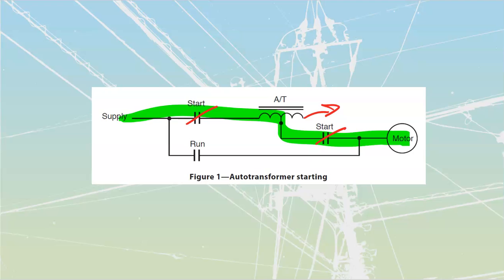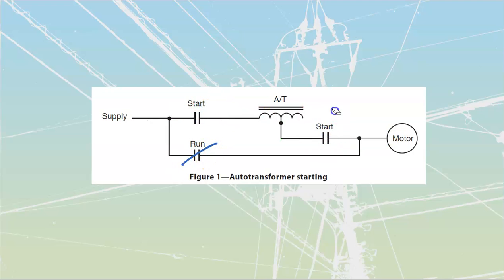And then when I go to a full complete run, I'm going to drop out this start section and then apply full value of voltage over to my motor windings itself. These are a very, very efficient form of startup. We don't have heat that is going to be burnt off in the same way as we do with our impedance type of starters.